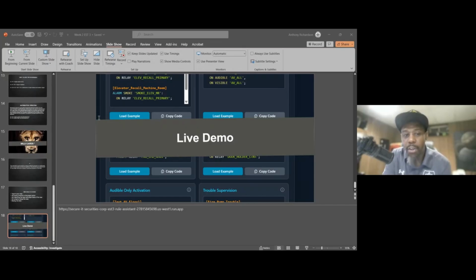Then next we want to turn on the strobes, which are the visibles. And then here they're doing something with the AHU and the RTU. So they're probably shutting fans down, or they could be purging the system. So on the manual pull station side, they have a Modcom. So they have Contact ID that they're using in this particular system.